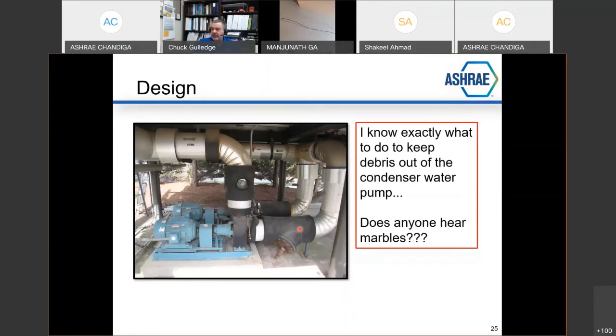So when we're picking condenser water pumps, we're always having to deal with paying attention to net positive suction head. We get a little bit of free energy, so to speak, just by atmospheric pressure. And then we get this little vertical head here that helps push the pump. And these pumps were actually picked to be at a safe point with their net positive suction head based on this geometry of that head and the atmospheric pressure on the water inside the basin.